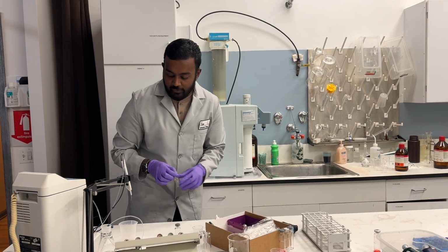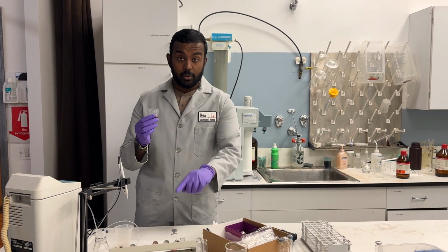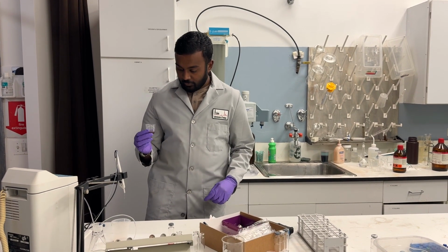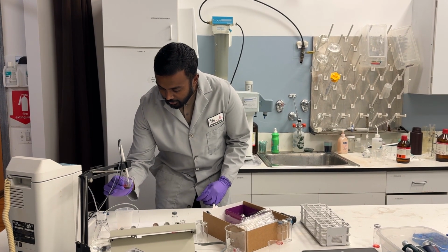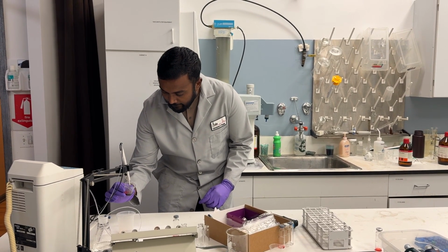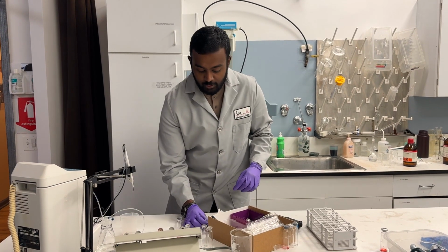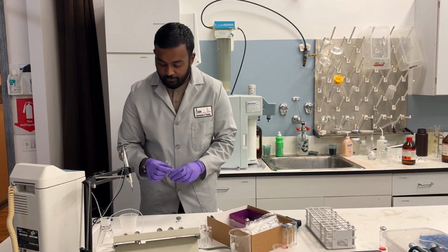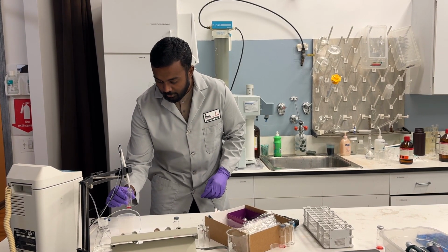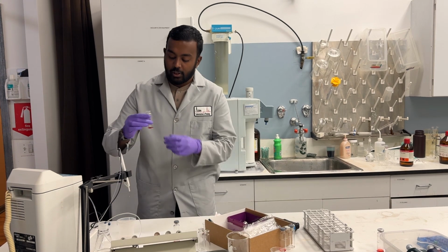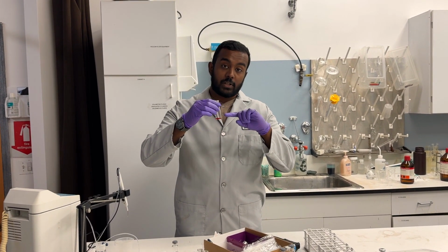Let me grab a fresh vial. Okay, so now we have our blood that we grabbed from the vial. So we're going to put it right up next to the auto-diluter. And you see how it kind of pulls the blood into there. We're going to grab a fresh vial, and it's going to run propanol right outside that. So what's going to happen is we're going to conduct what's called headspace analysis.